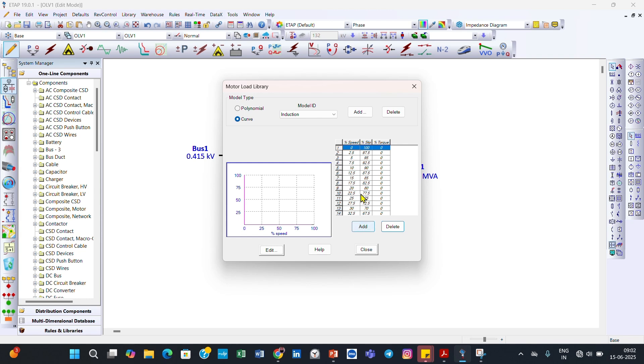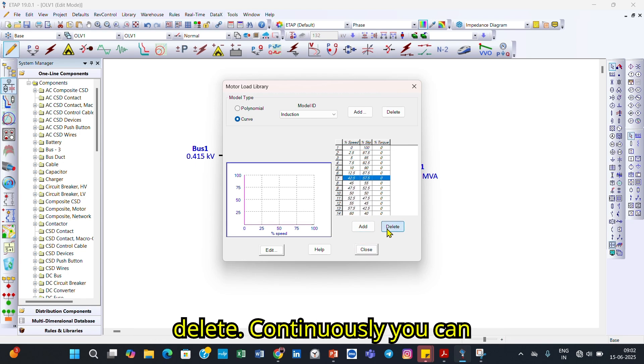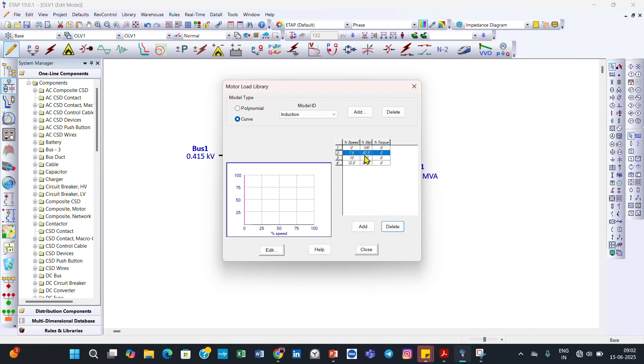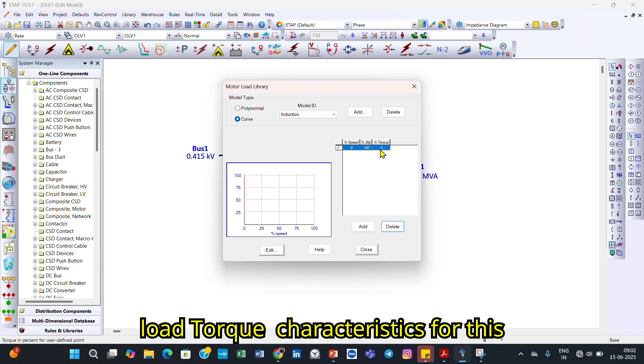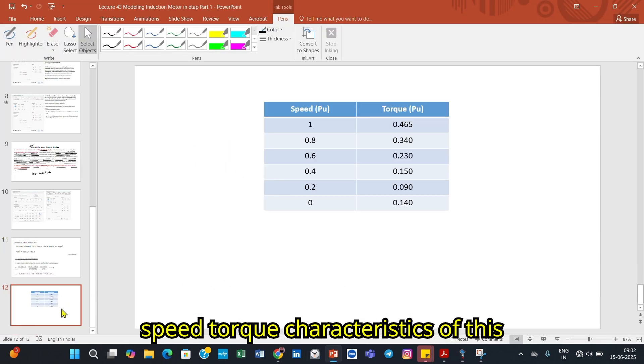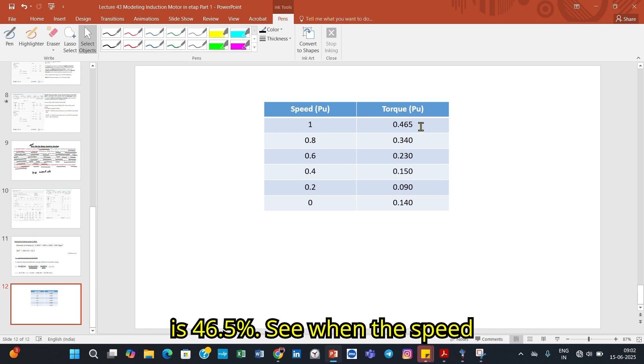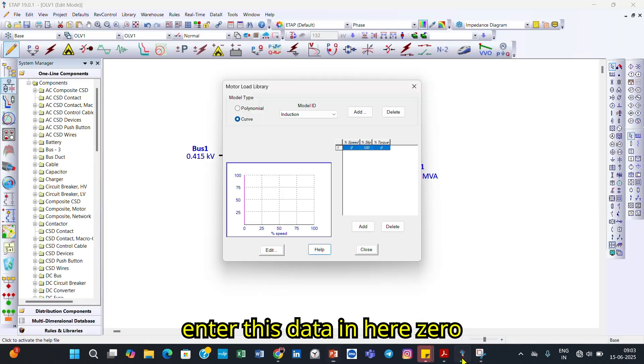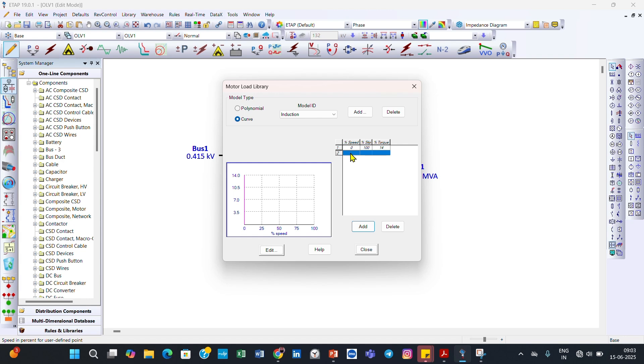Now we have the speed-torque data entry screen. I delete the existing default data points one by one. For the speed-torque characteristics of this motor: when speed is 0%, torque is 14%; when speed is 100%, torque is 46.5%. I begin entering these data points — at speed 0, torque is 14.